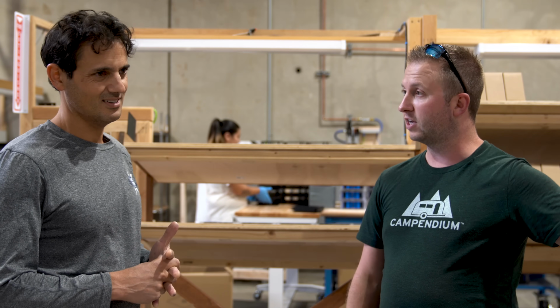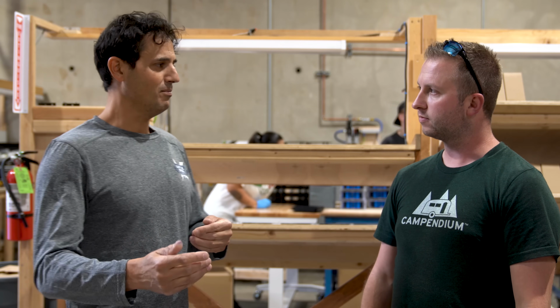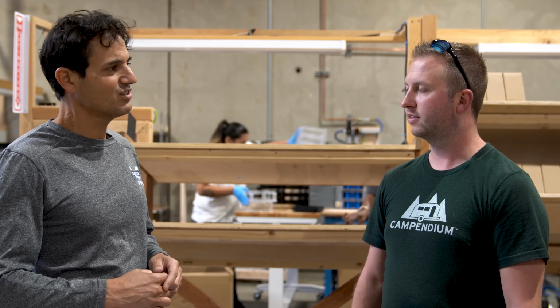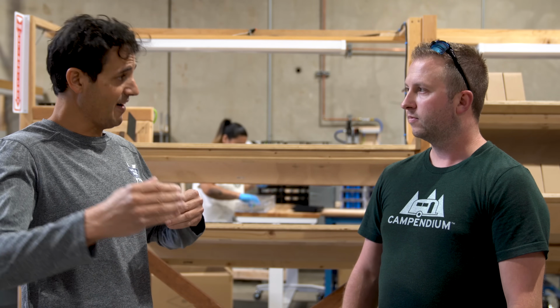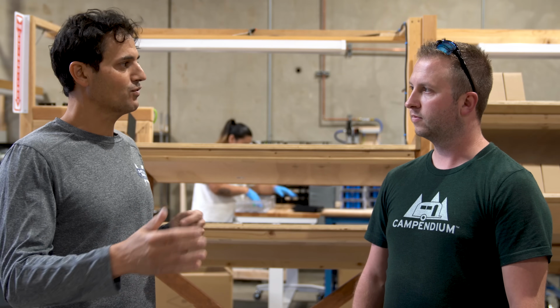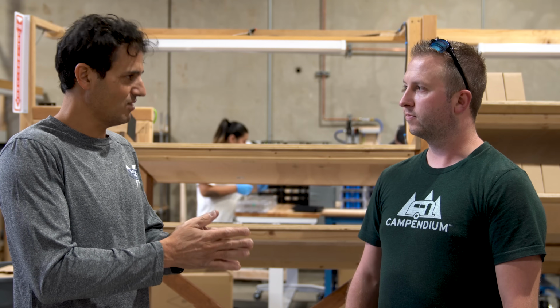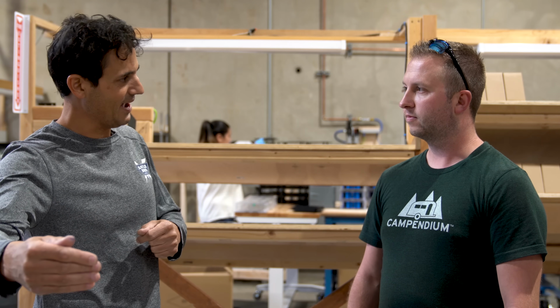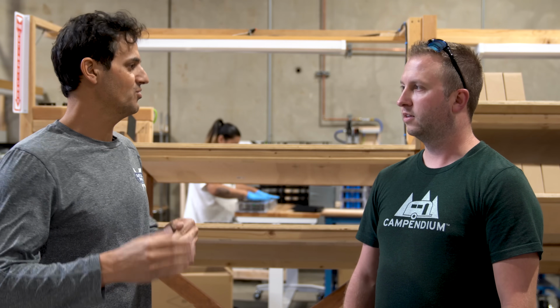And then every battery that leaves here, you're basically guaranteeing has at least 100 amp hours of capacity, because you've tested the cells and the modules and the battery itself, right? That's right. We match them based on capacity, which means we know the capacity of every battery. Our capacities generally range between about 103 and 108. So we do get a variation from pack to pack, and that occurs because we don't mix up capacities. The fact that we keep everything identical actually amplifies the variations in the packs at the end. So we've got about a 5% variation, but they're always at least 102, 103 amp hours.